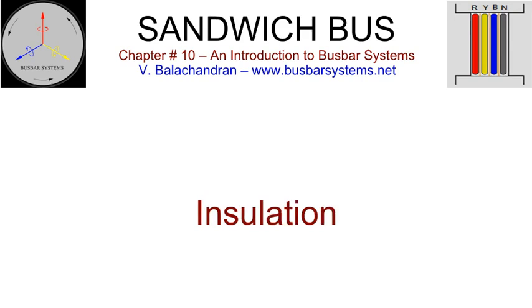Insulation. Most manufacturers have adopted epoxy coating or mylar wrapping as the primary insulation for the conductor. Some manufacturers adopt a combination of both. Mylar is a registered trade name for biaxially oriented polyethylene terephthalate (BOPET) insulating material. It has good dielectric and mechanical properties. It can be wrapped around a conductor. Since the film is thin, it transfers the heat across the insulation efficiently.